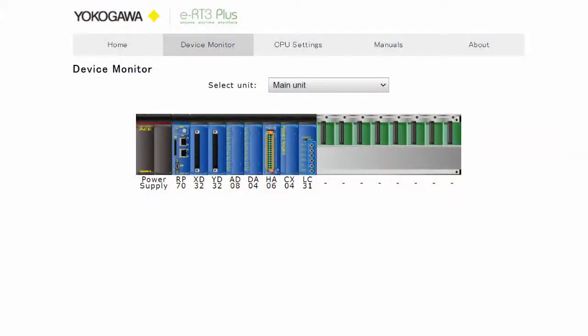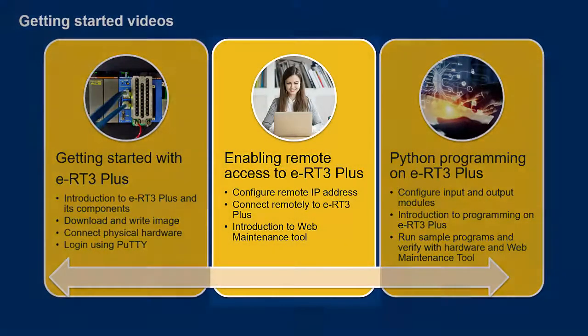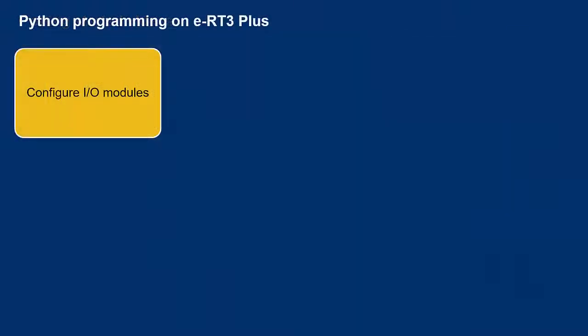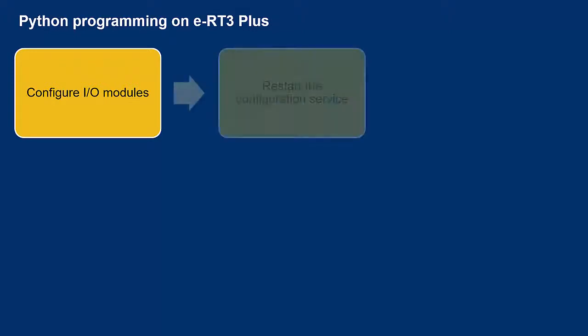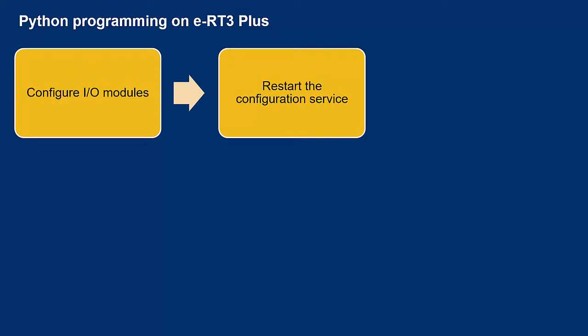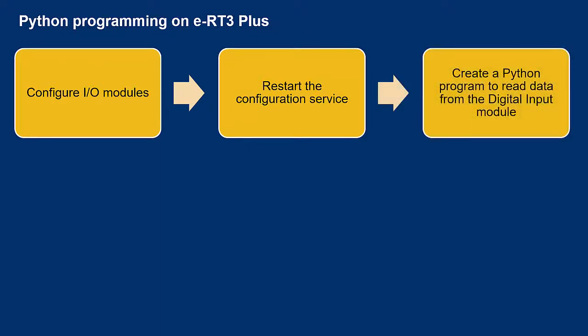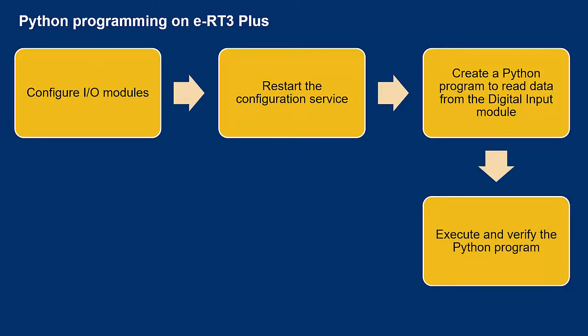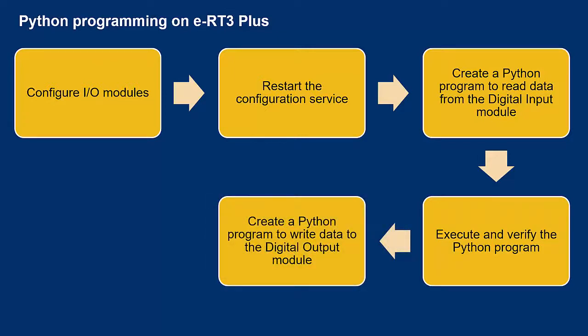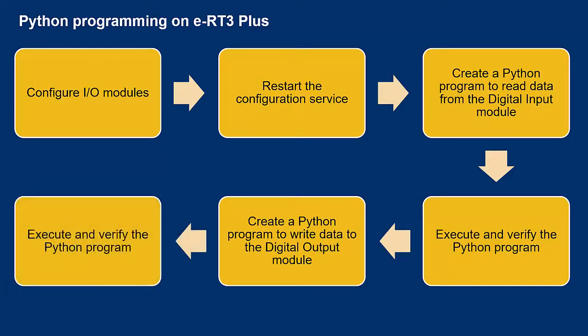We then verify the output of the programs on the web maintenance tool, and also verify the same on the IO modules physically connected to the setup. To execute a Python program on ERT3 Plus, first we modify the settings in the IO configuration file according to the connected modules, then restart the IO configuration service. Next we create a program to read data from the Digital Input module, transfer it to the device, execute it, and verify results. Similarly, we create a program to write data to the Digital Output module.